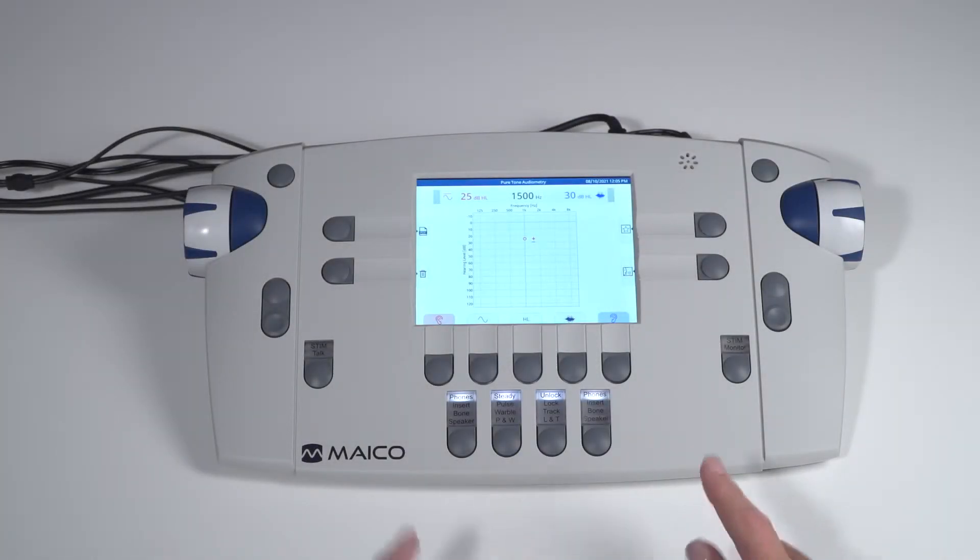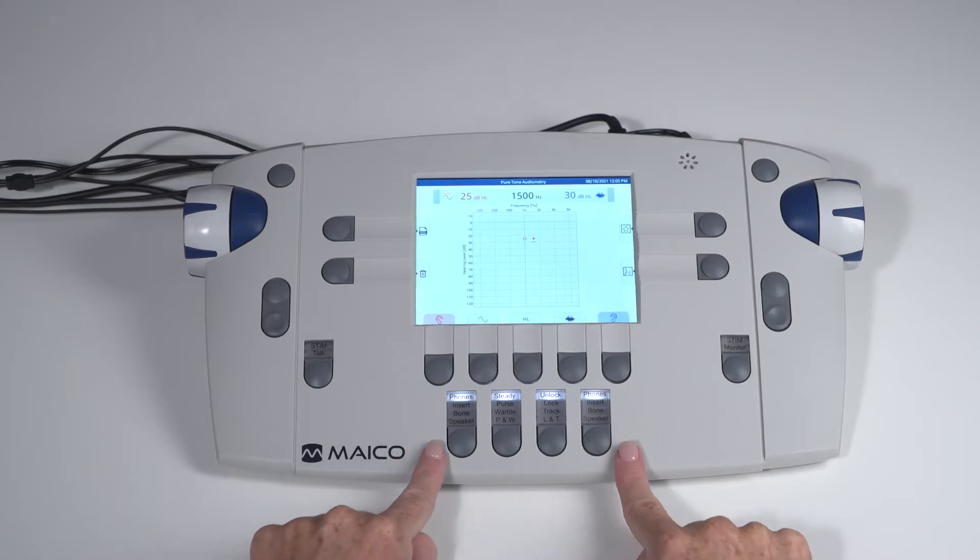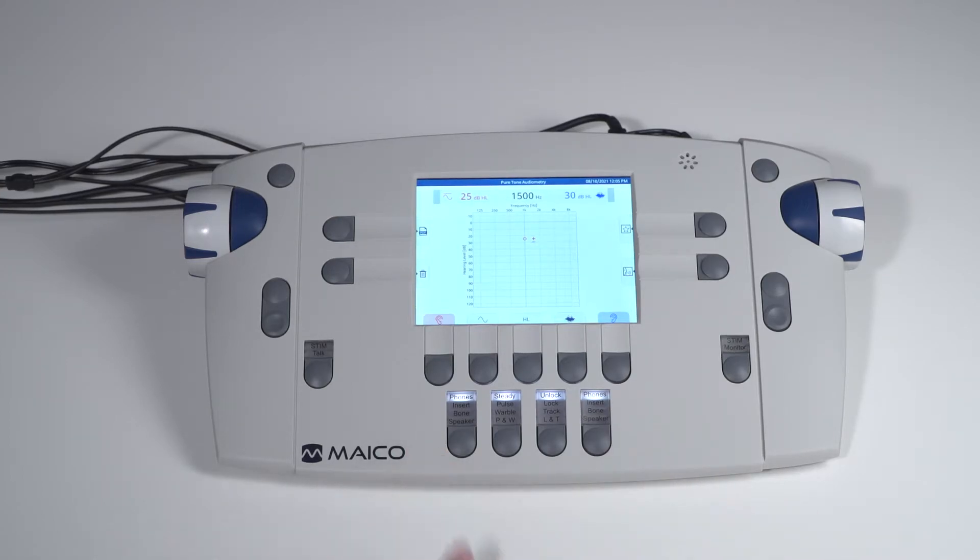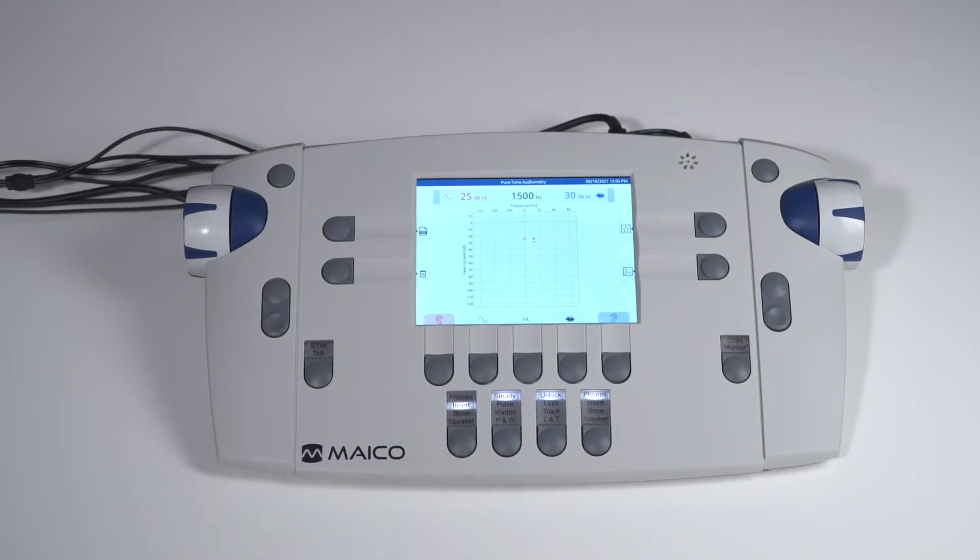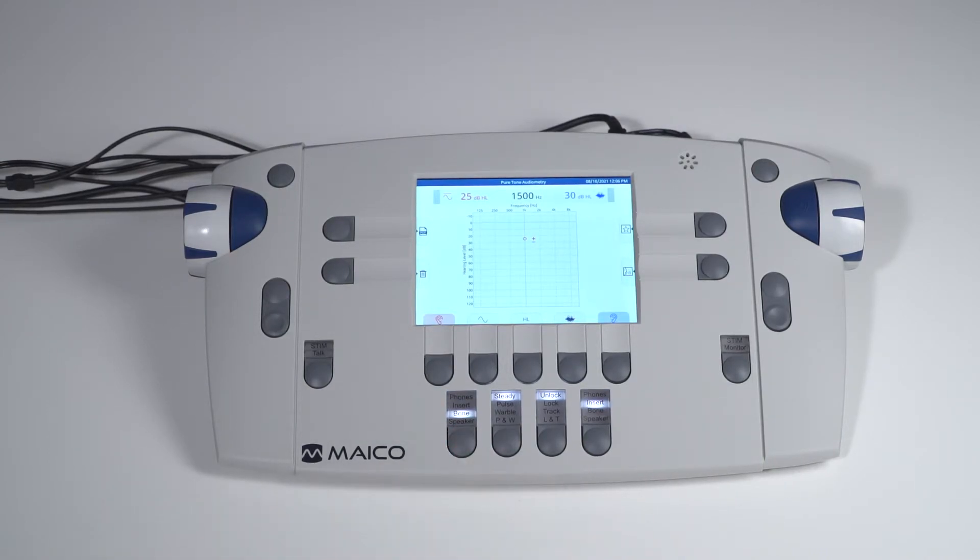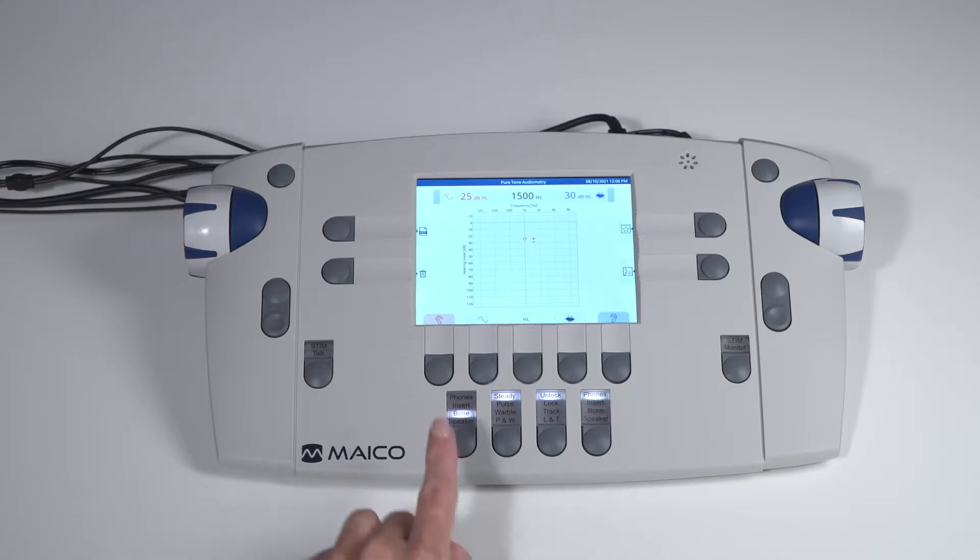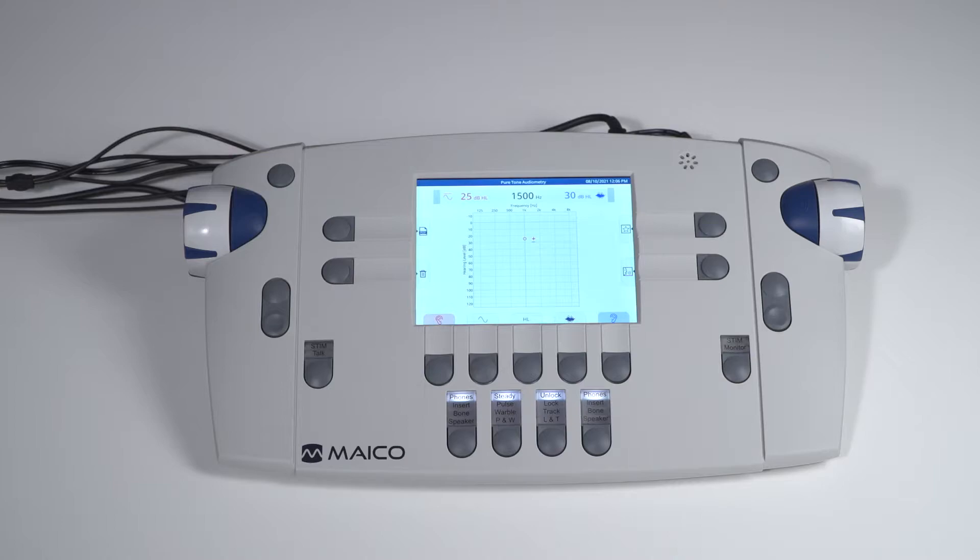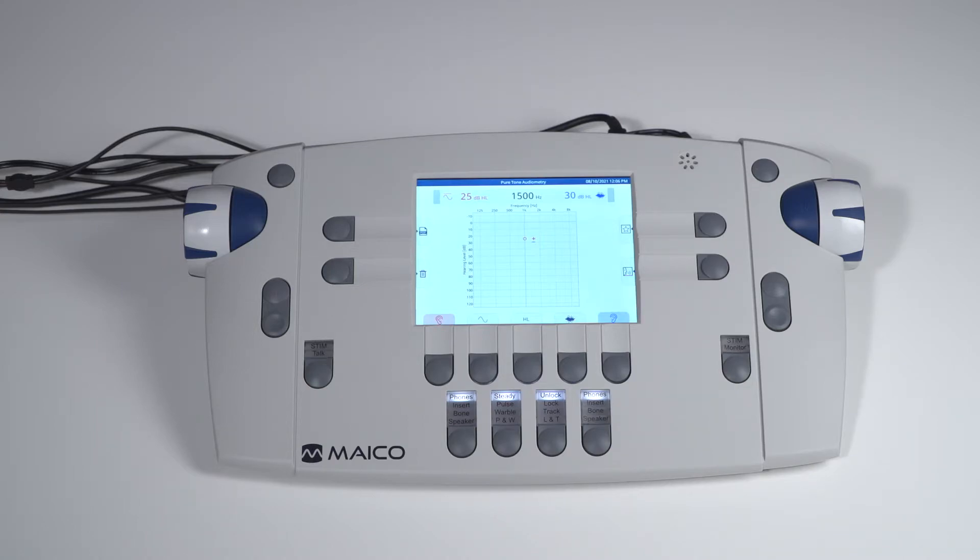Transducers can be selected with the two outer keys, one for each channel. Press the key to toggle through the selections. If a selection does not light up, it is not calibrated and therefore not selectable. The device will automatically change both transducer types with the push of one transducer key with the exception of bone. Just confirm both transducer keys are correct before proceeding with the test.